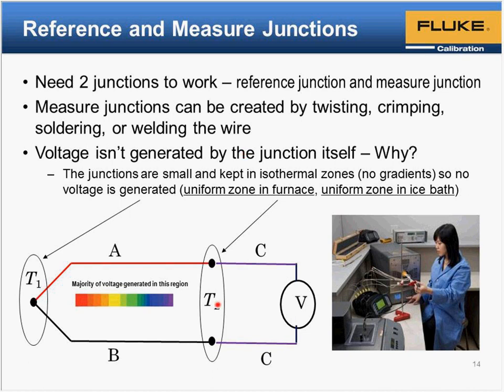And we do that by either in an ice bath or some temperature. It can be even just a liquid bath, the temperature of it, because you have another temperature sensor telling you the temperature. Or if connecting to the meter, we'll tell you here a little bit more about what happens then when wire is connected to copper connectors in a meter.